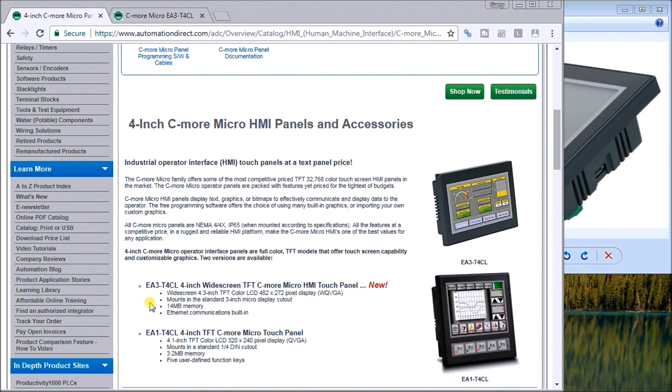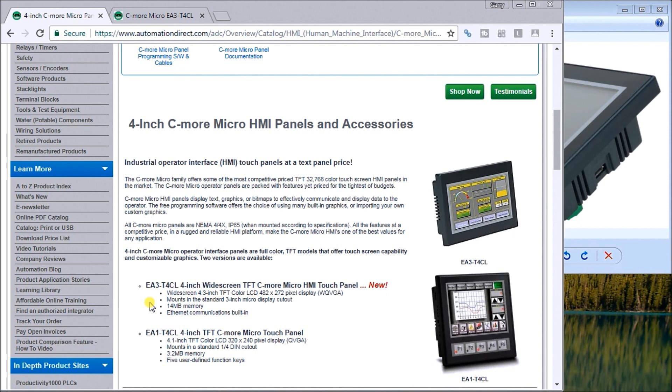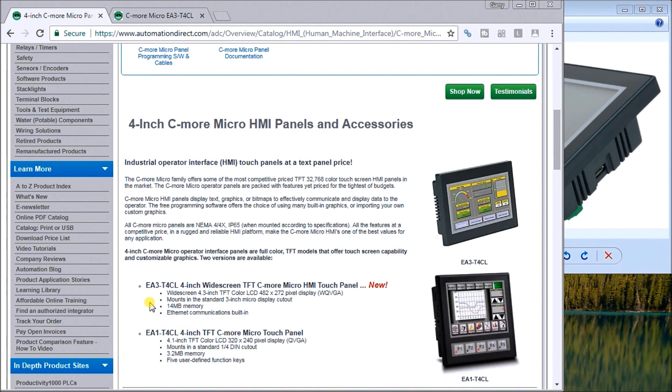What this is is a human machine interface made to display and control operations for your automation solution. Information is displayed in a graphical format, the graphical user interface, sometimes referred to as the GUI. The HMI is usually part of a SCADA or supervisory control and data acquisition system. Communications from the HMI to the control is usually done through a serial connection like RS-232, RS-485, or RS-422, or Ethernet which is an RJ-45 method. They also have different protocols depending on the manufacturer of the controller. The automation control device is not limited to a PLC; you can also communicate to drives, temperature process controllers, etc.